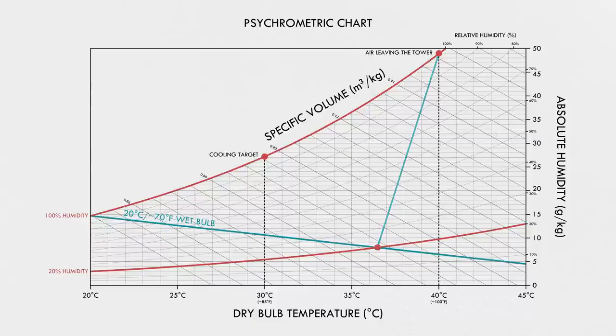But it doesn't go in a straight line. Since the air is coming in from the bottom, it's not coming into contact with the warm water but the coldest water first. So it actually heads toward the outlet temperature and gradually veers toward the water inlet temperature as it rises through the fill.